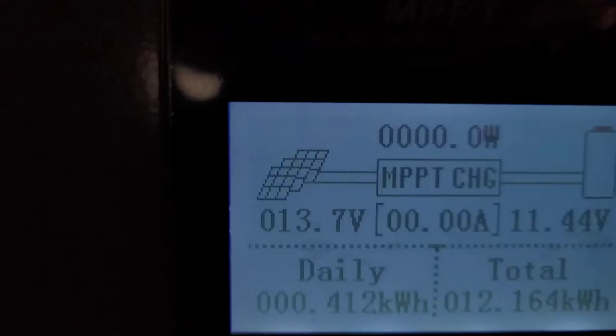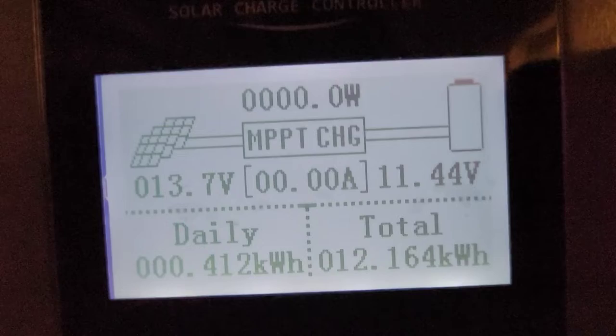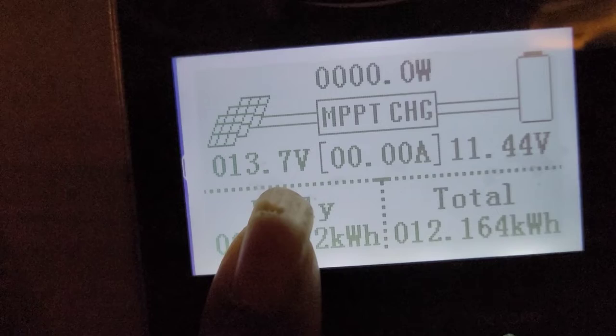The solar is on — let's turn it off, so we're going to unplug it. Now let's go back up here and get a good look at this. We can see where the battery is, and the voltage coming in from the Renogy is at 13.7.